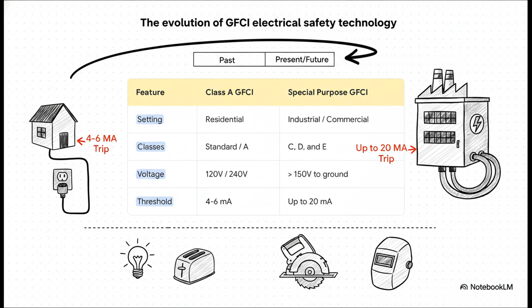So why the huge difference? It's because heavy industrial machines can have a natural, totally non-hazardous leakage current when running, it's just part of how they work. An SP GFCI is calibrated to ignore that expected normal leakage while still being sensitive enough to protect a person from a genuine, dangerous fault.